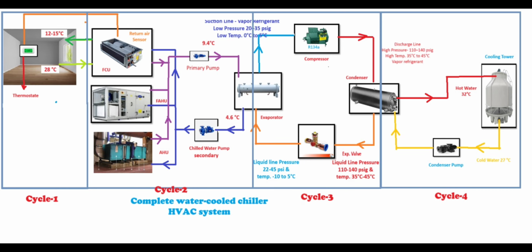The air is at 28 degrees. When this FCU starts, this AC which is above your ceiling, fixed inside your room or office, it will start and suck air from here and supply air here. It is sucking 28 degrees Celsius and supplying 12.5 degrees Celsius.